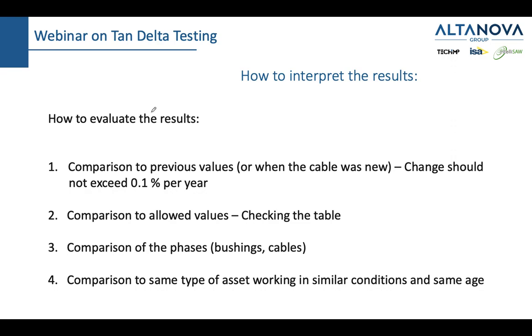Now, moving on, how to interpret results. Also, I'm having some questions about negative values of tan delta in a transformer, so let me address that right away. There are a few reasons why you could get a negative value for the tan delta. One of them is you are not performing the test properly. This is very often the reason. It's a sign that you didn't connect something correctly. Another reason could also be that the grounding of your substation is not done properly, because then you are not able to properly measure tan delta. Grounding is essential because we also measure the current going through the ground.